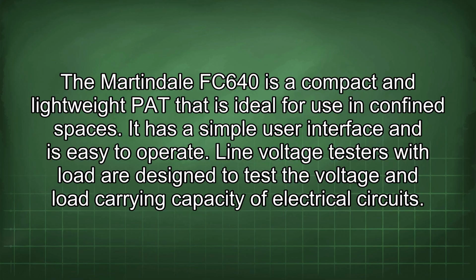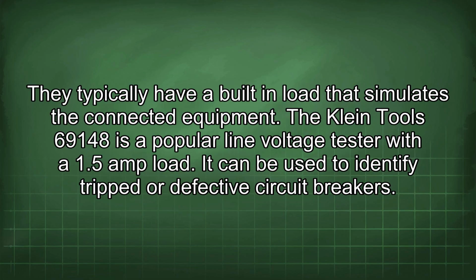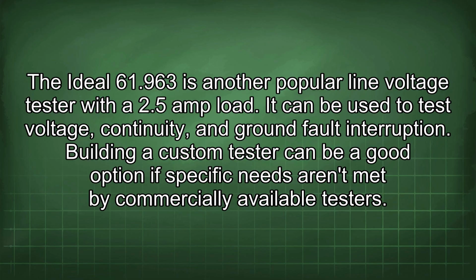Line voltage testers with load are designed to test the voltage and load carrying capacity of electrical circuits. They typically have a built-in load that simulates the connected equipment. The Klein Tools 69148 is a popular line voltage tester with a 1.5 amp load. It can be used to identify tripped or defective circuit breakers. The Ideal 61963 is another popular line voltage tester with a 2.5 amp load. It can be used to test voltage, continuity, and ground fault interruption.